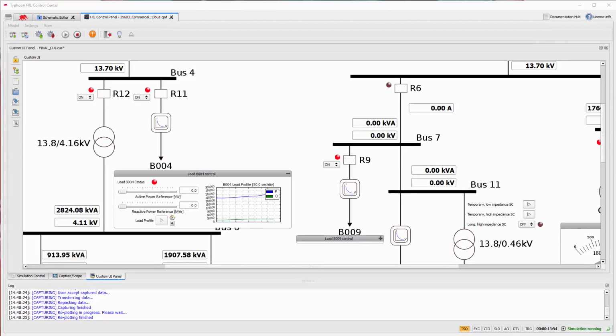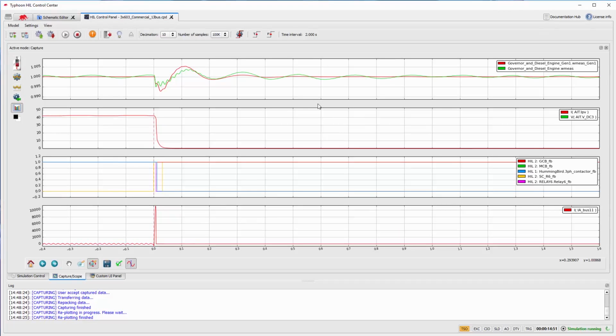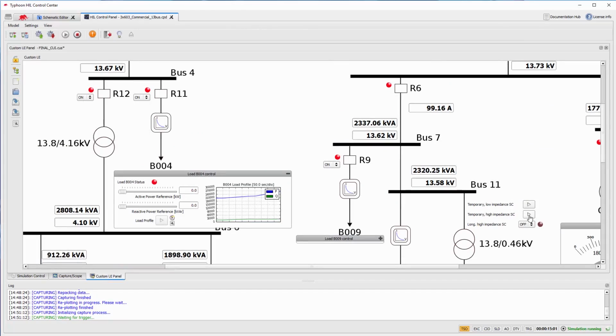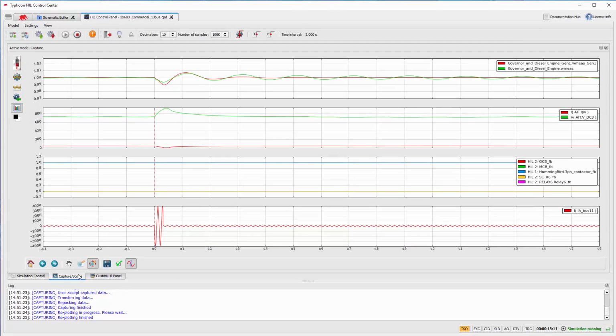Let us set the trigger for the high impedance contactor called SCR7 and do a capture the same way we just did. This short circuit has an impedance of 4.5 ohms and thus its current is expected to be around 2.8 kiloamps. Let us enable the trigger and cause the fault. As we can see, the short circuit current matches the calculation.